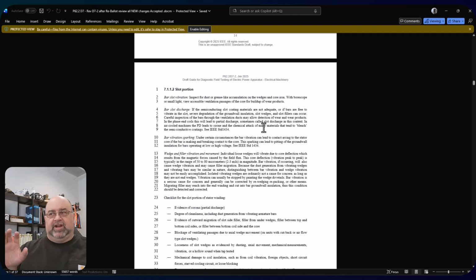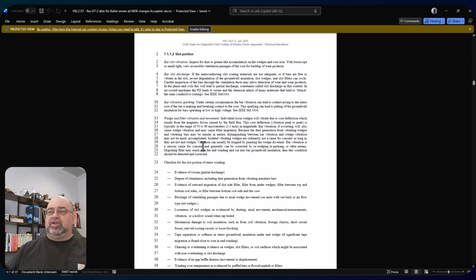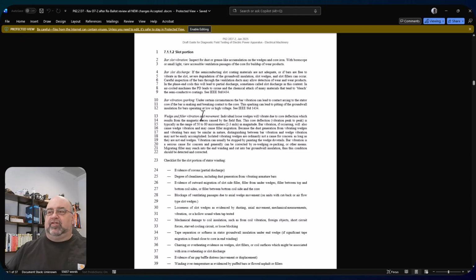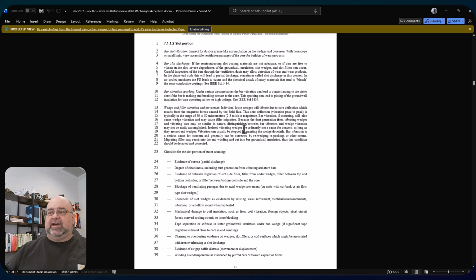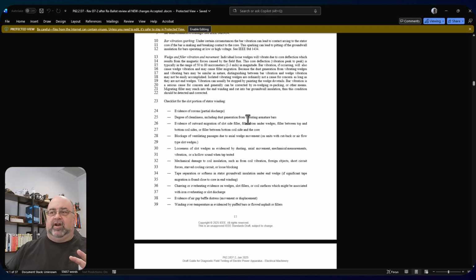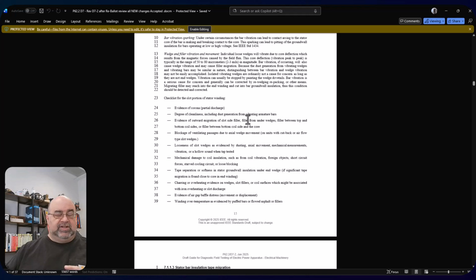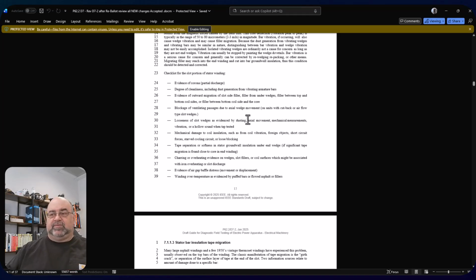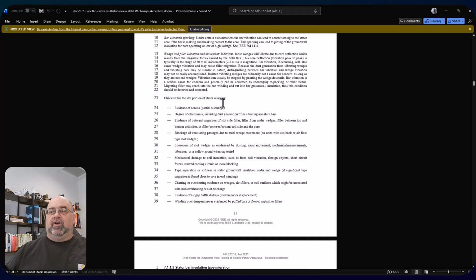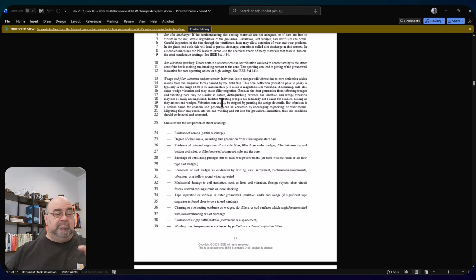Everybody says there's powder there—it's not powder, it's bleached insulation, with a lot of pits that make it look whitish. There's also bar vibration, sparking, wedge and filler vibration and movement—basically looking at loose wedges, etc. Now this is an area where electrical signature analysis and current signature analysis really have strengths, for coil movement as well as magnetic wedges in particular.